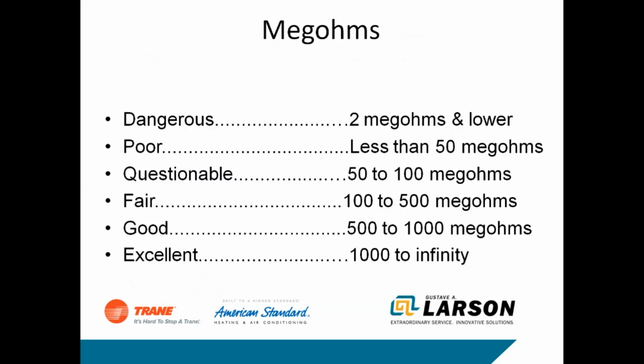So if you do use megohms, megohms are a good way to look at things if you have a record. If you just put it on there and try to determine if it's good to ground or if there's something going on with the system, it may not always be the best way. But this is just a chart that says if it's 1,000 to infinity, it's in good condition. If it's 500 to 1,000, it's in good or excellent, then good condition. If you have a ground, it'll show up. So these are the values that you're looking for if you're checking for a ground on a compressor.